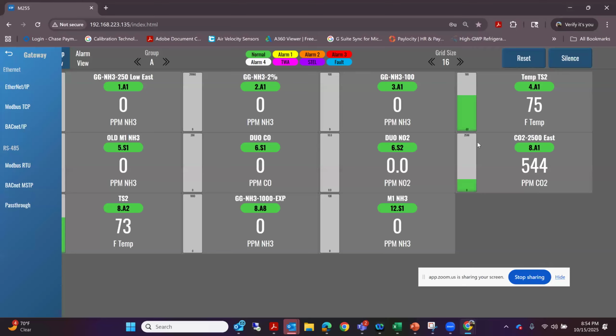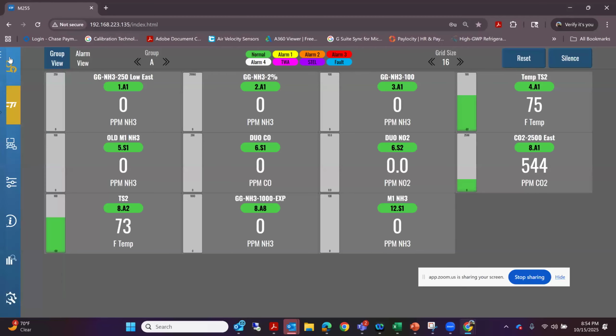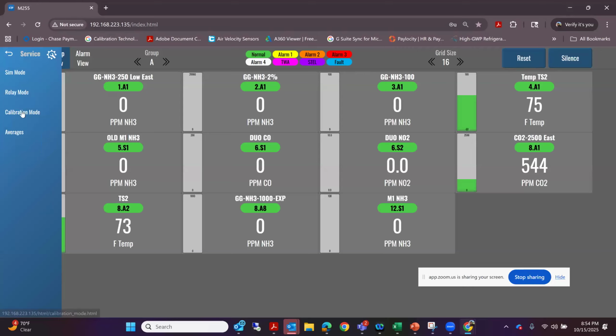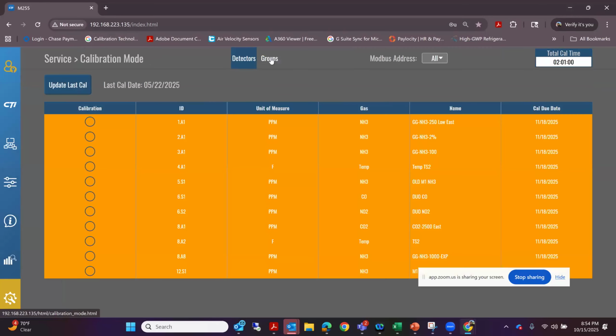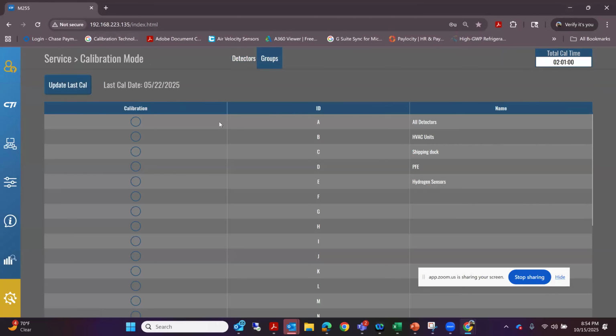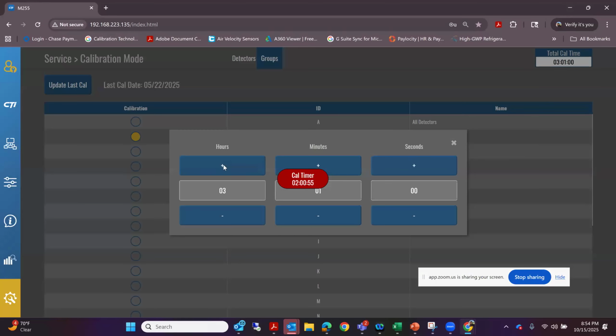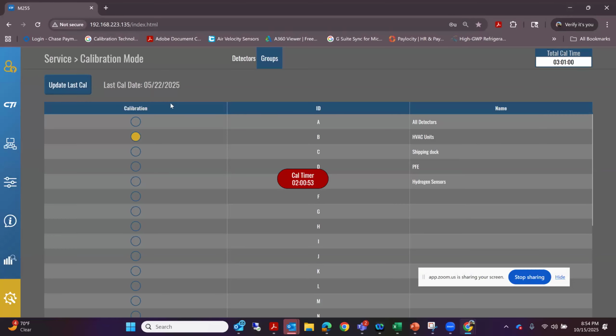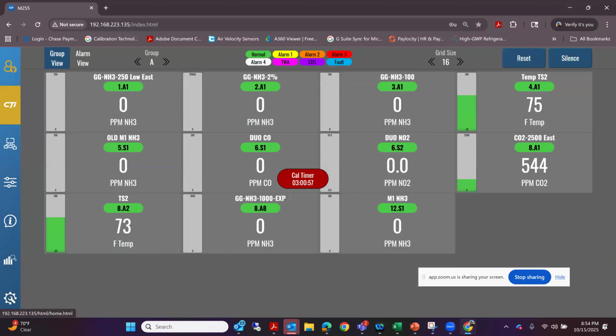And then that gets you a nice little GUI, and you now have the capability of tripping any relay on the system if you want to. If I want to go to calibration mode, it's pretty simple. I can go here, and if I want to go to a group of sensors on the roof, I can say, hey, there's my HVAC sensors on the roof. I'm going to just go calibrate them for right now. And so I need 3 hours to time this, so I'm going to jump my timer up to 3 hours. There we go. I'll stop it and then restart it with 3 hours. There we go. Now everybody knows that we're in cal mode on some group of sensors out here somewhere.